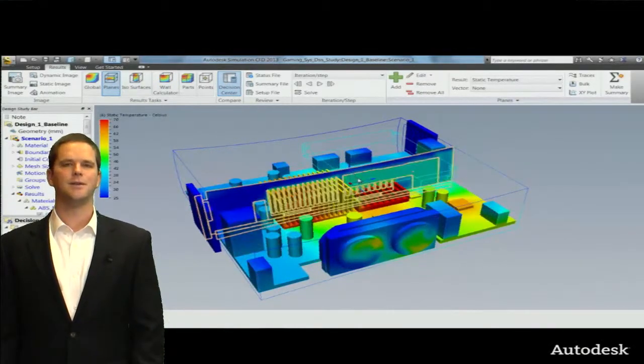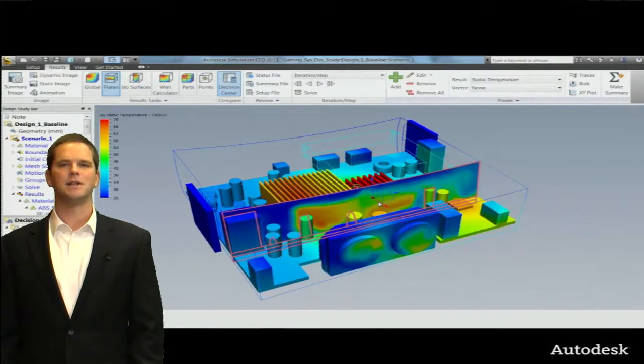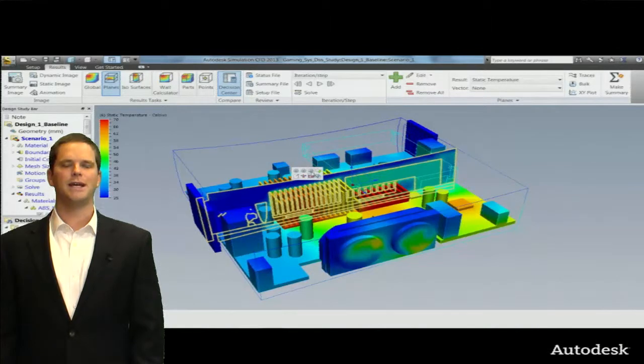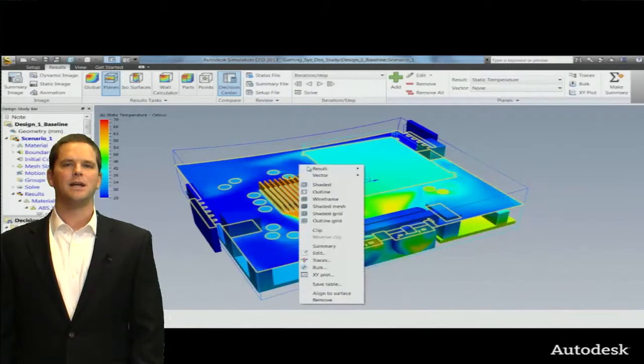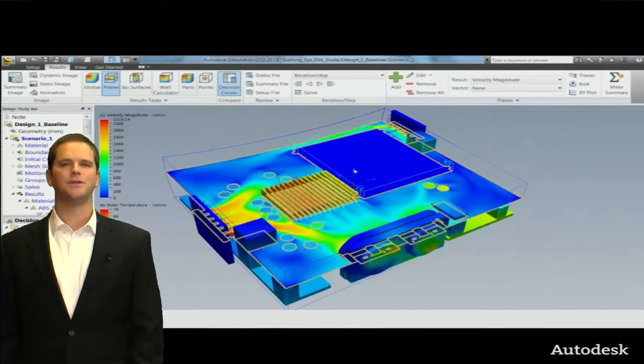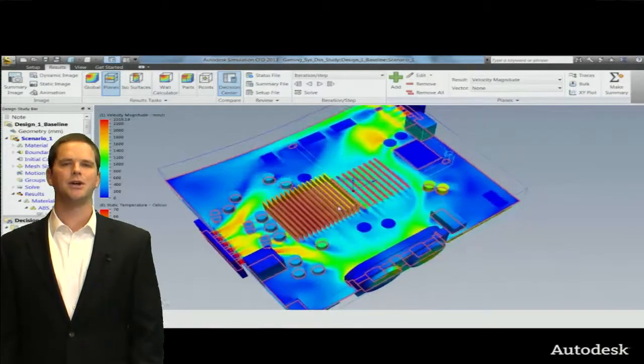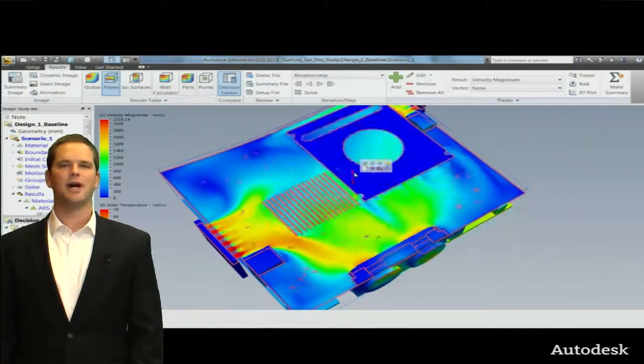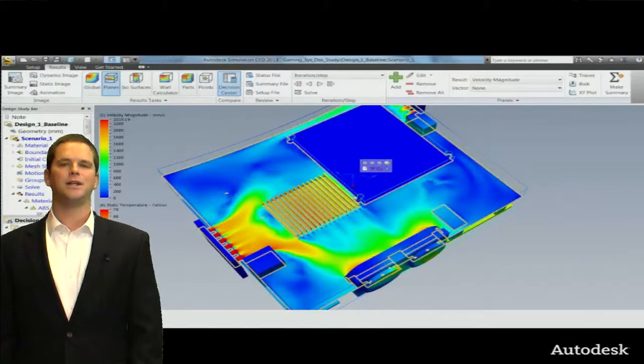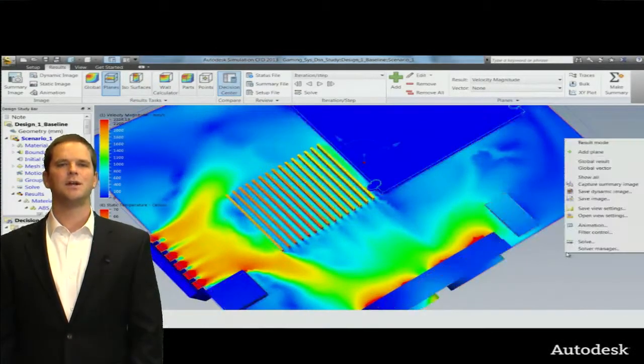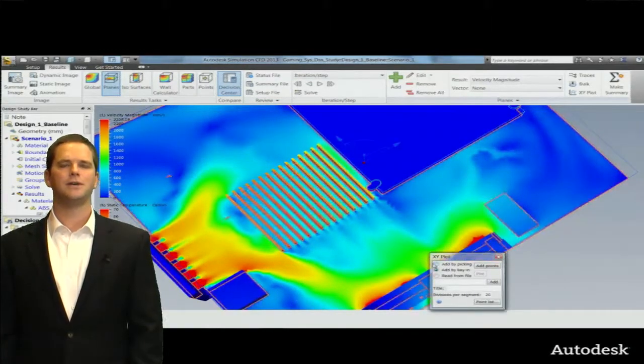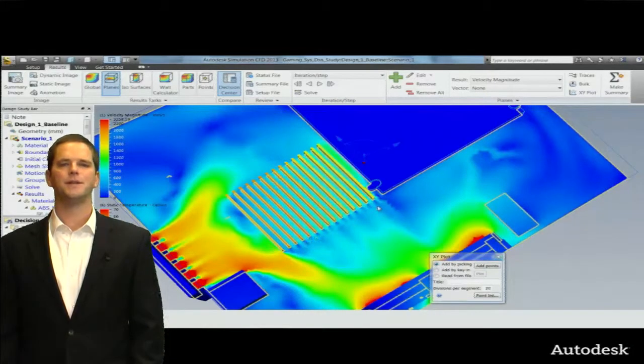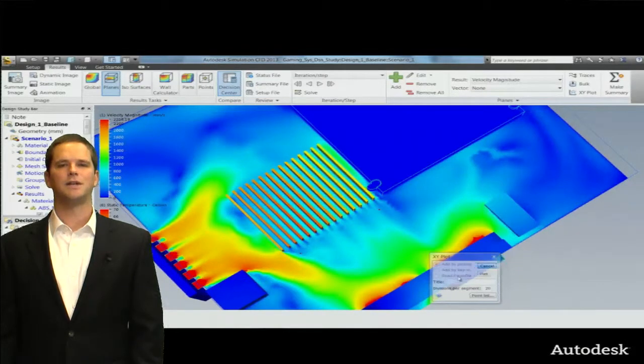We can see the thermal profiles. We can see the thermal plume coming off the heat sink. We can take this cut plane and slice and dice through the model and basically look at any point within the model. We can plot this up, get qualitative or quantitative data, and then what I'll typically do is I like looking at temperatures on the solids and then flipping the cut plane over to show velocity. So we're showing the speed of air through the unit. We can see it streaming around the heat sink and a majority of the flow is actually bypassing the heat sink and going straight to the fan. We can even see the biasing on the fan of the temperatures and that's just a result of it totally missing the heat sink. So we want to do something. Now we're already thinking about design changes. We want to go back and do something to normalize the flow through the heat sink.